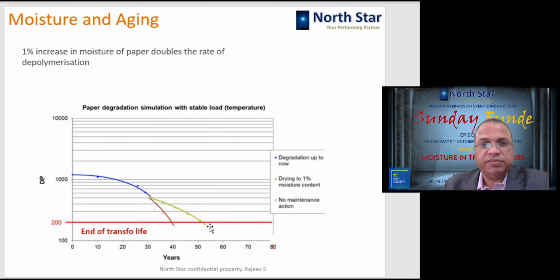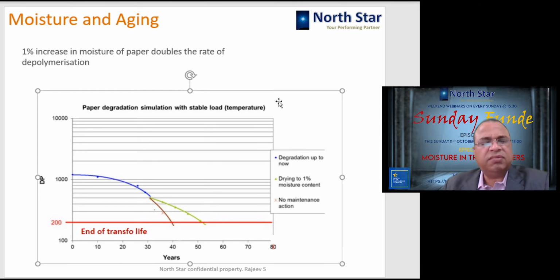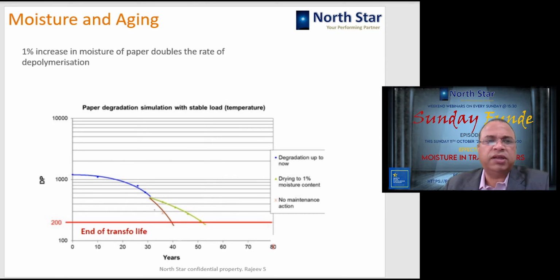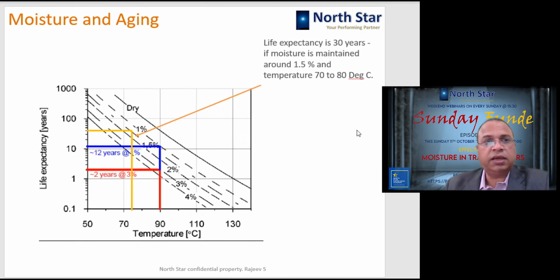So what does that mean? That if the moisture is controlled inside the transformer, then the life of the transformer can be enhanced, meaning the rate of aging can be reduced, and the transformer can serve you for a longer time. A very broad thumb rule is that every 1% increase in moisture in the paper doubles the rate of depolymerization or reduces the life by 50%. Okay.